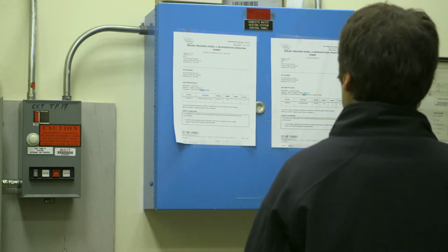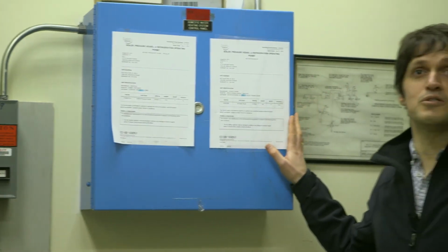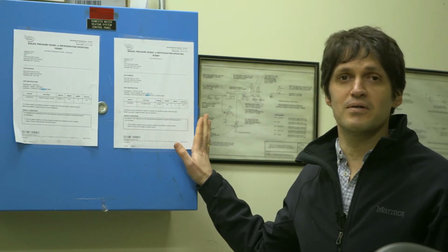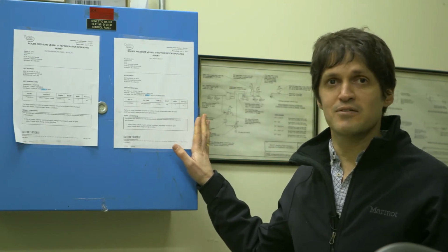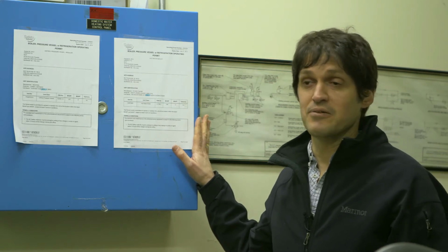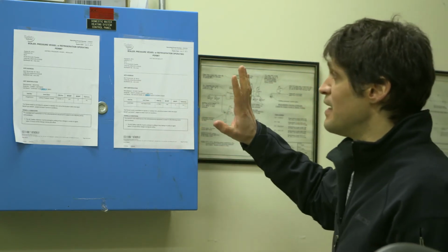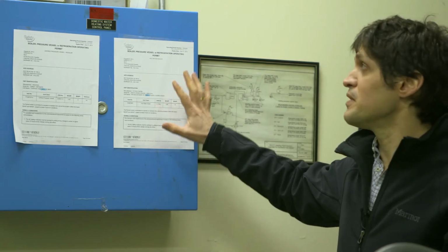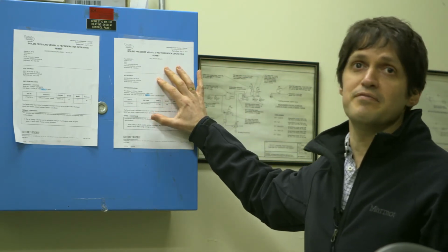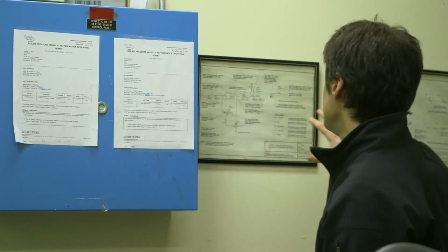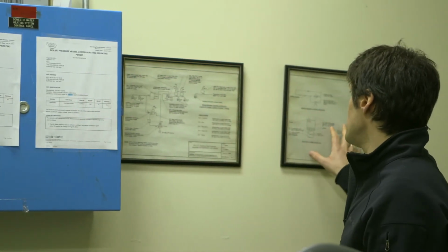A very important thing to look at when we look into a boiler is how they're controlled. Often you'll see that there's a lot of opportunity with boiler control because if they're not controlled well, they could operate very inefficiently. So know how the boiler is controlled. In this case, look at your control panel if it exists at all, and look at control drawings that would be available typically in the mechanical room or in a boiler room.